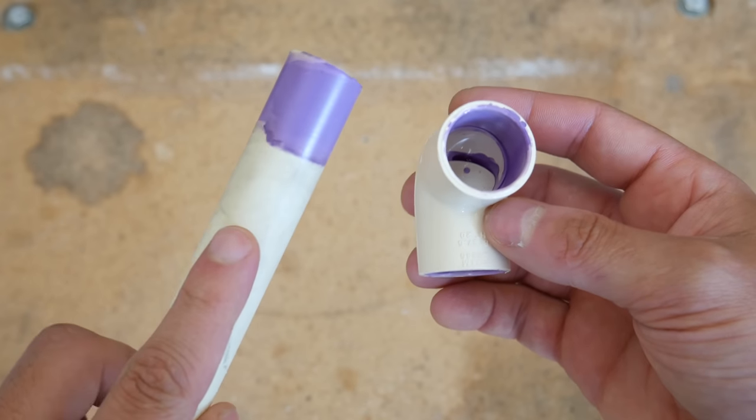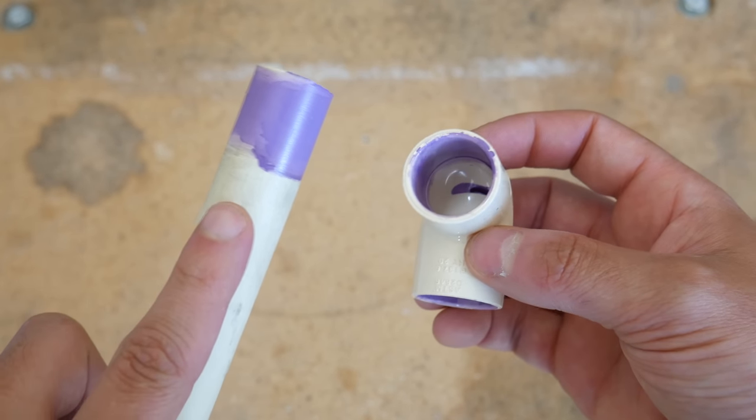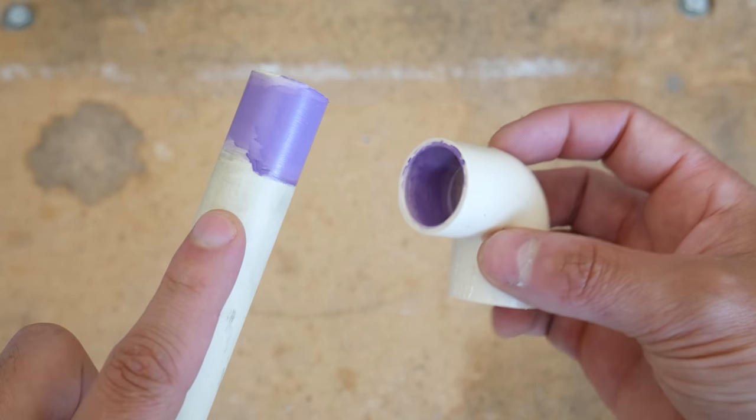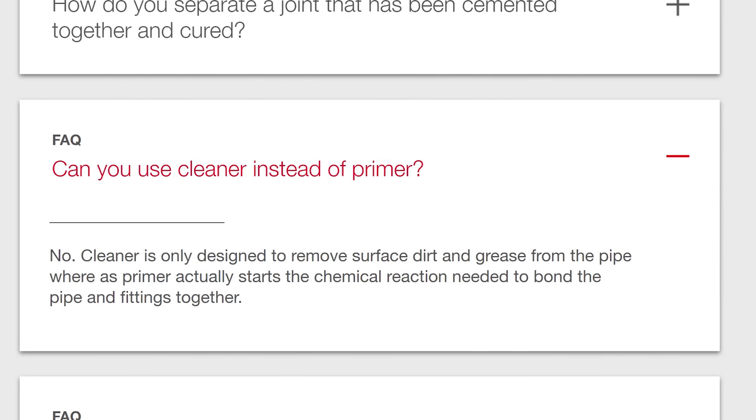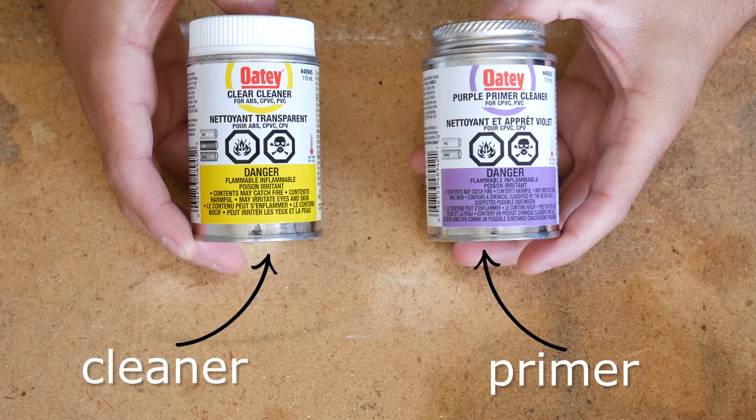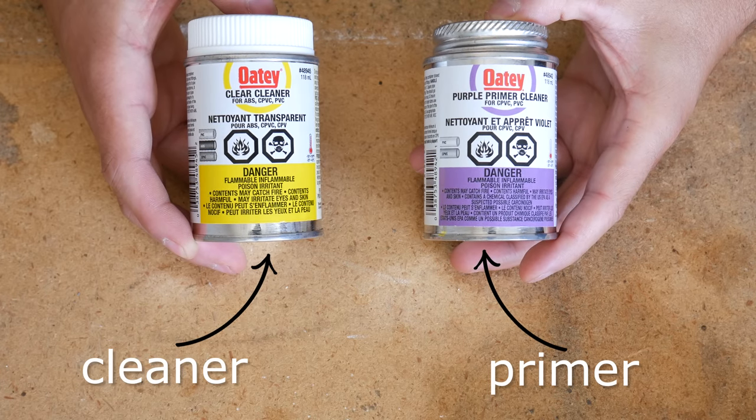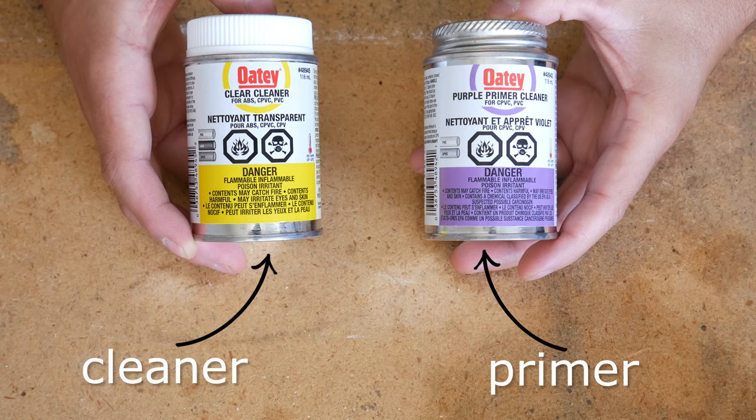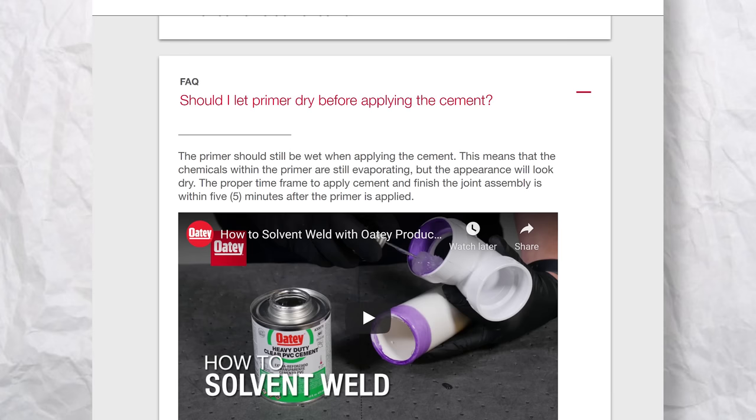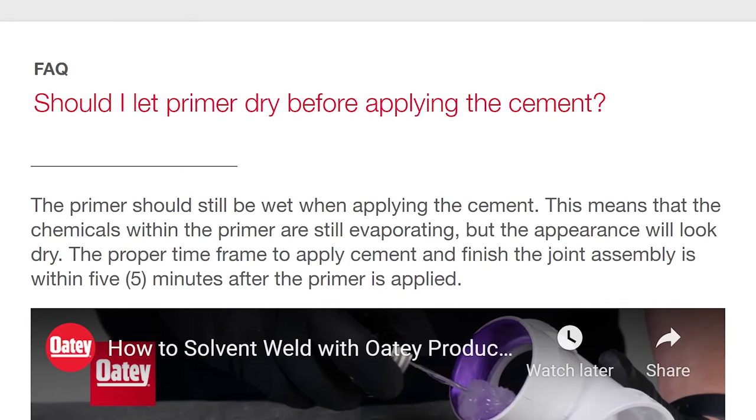Number five is not priming PVC or CPVC before cementing them together. Contrary to popular belief, priming is not cleaning. Priming a fitting and pipe actually creates the chemical reaction needed that allows them to properly bond together. Furthermore, cementing or gluing should be done within five minutes of its application as per Oatey's instructions to ensure a proper bond.